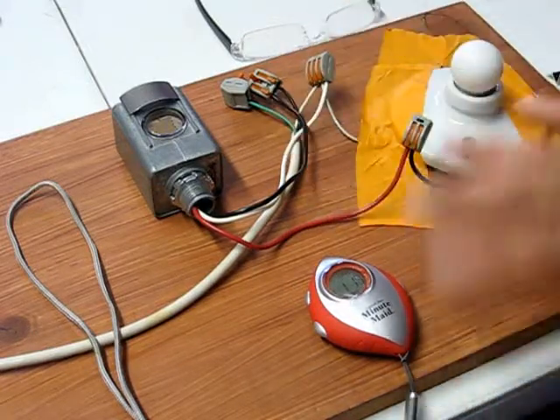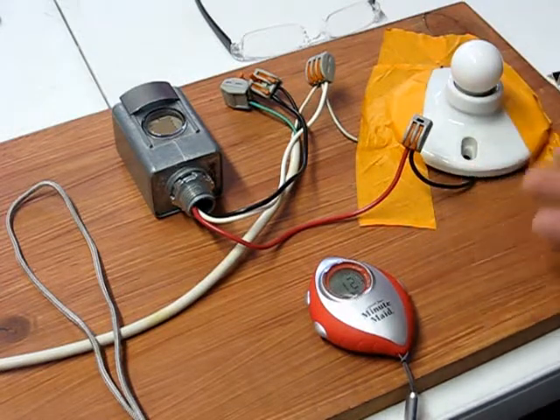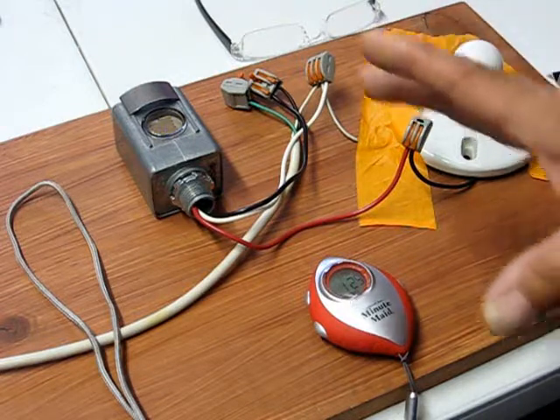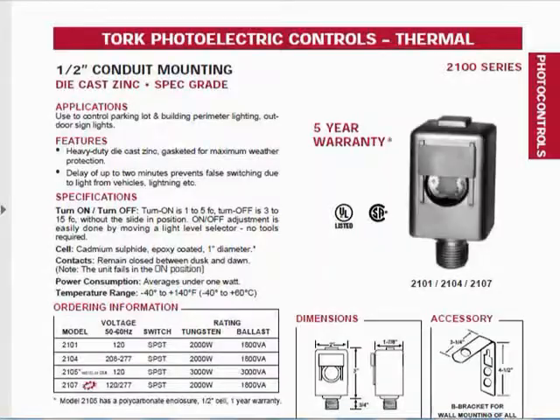These time delays are going to vary. When I first turned this on this morning, I let it warm up a little bit — it took two minutes for it to switch either on or off. Here's the spec sheet. You can see there are three different models: one for basically 120, 208, and 277 volts.